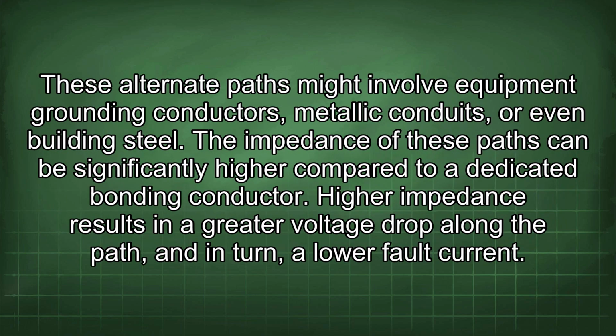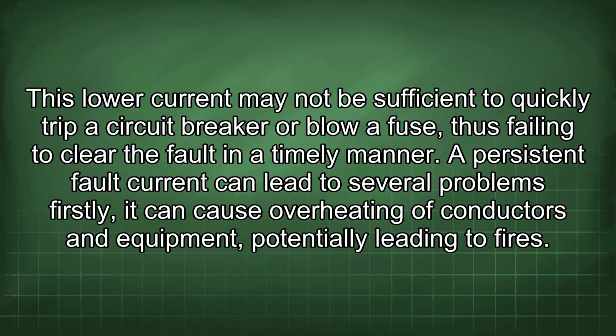These alternate paths might involve equipment grounding conductors, metallic conduits, or even building steel. The impedance of these paths can be significantly high compared to a dedicated bonding conductor. Higher impedance results in a greater voltage drop along the path, and in turn, a lower fault current. This lower current may not be sufficient to quickly trip a circuit breaker or blow a fuse, thus failing to clear the fault in a timely manner.